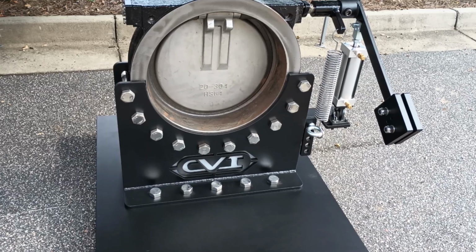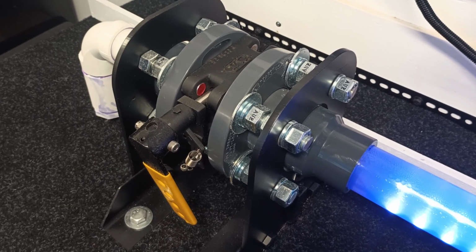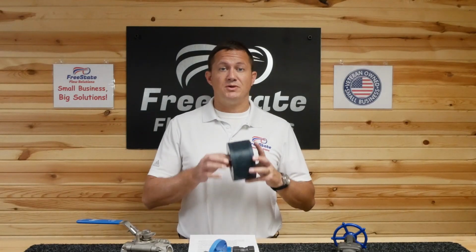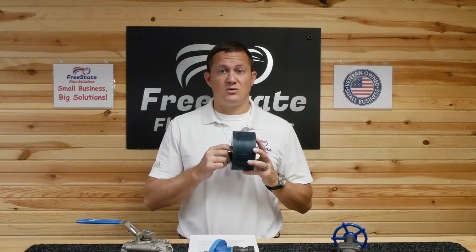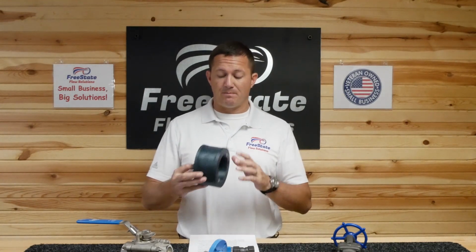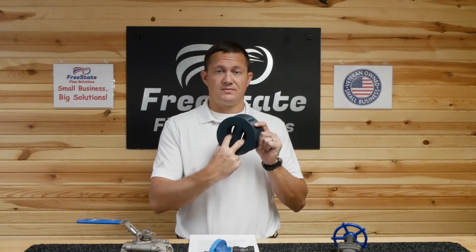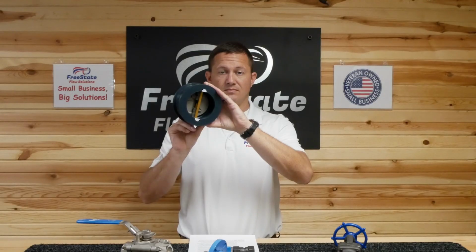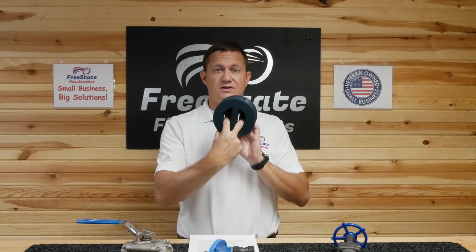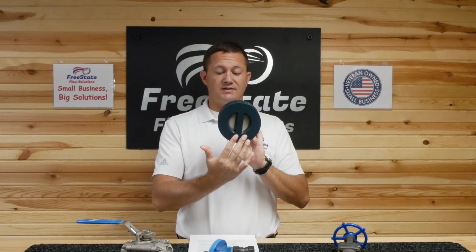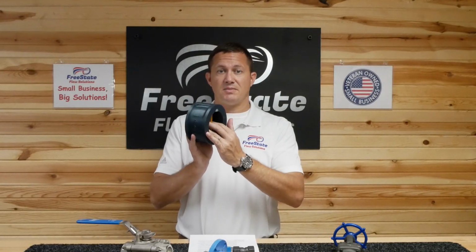There are other styles of valves that do not require outside intervention in order to operate, whether by hand or by actuator. Check valves being one type, open when there is flow, and then close when there is a drop in flow or pressure. This is in order to prevent backflow. So as water comes in here, it opens up the check valve, as you can see, and then as the pressure drops off, the check valve closes, and it does not allow for water or whatever fluid you might be using to come back this way.